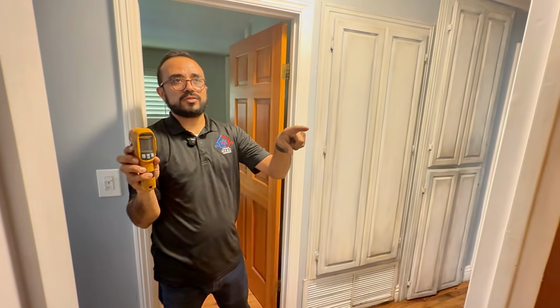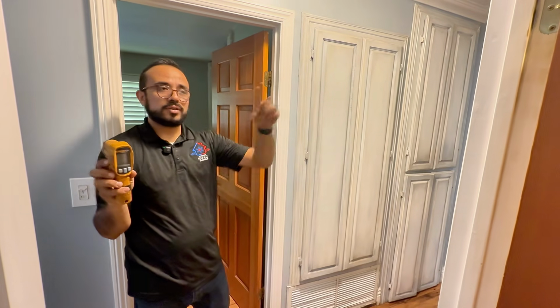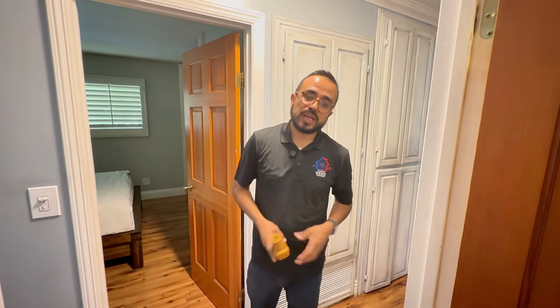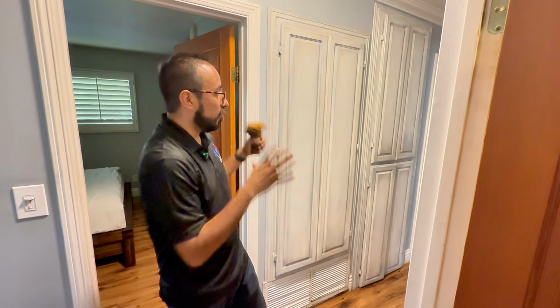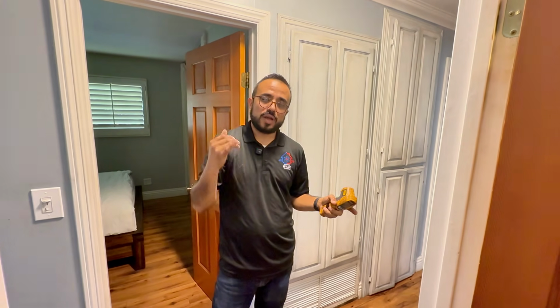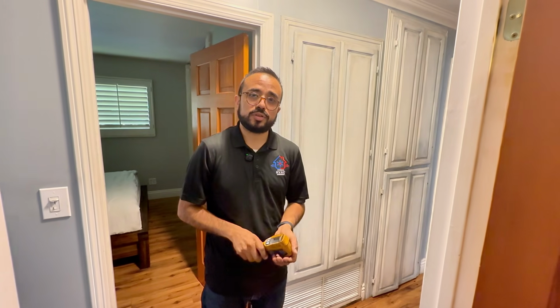Okay, look at that, 51. So 72 minus 51, what is that? That's 21, right? 72 minus 52, that's 20. So about a 21-degree delta T. The system is working great, even though it's a bit oversized, but at least for the way it's operating, with the things that are already installed, it's working great. So we have a good superheat, good subcool, and a good delta T. So this system is doing great. It didn't need much in regards to maintenance besides checking the capacitors and making sure we clean the coils. But let's head outside. I'm happy with what I'm seeing right now.